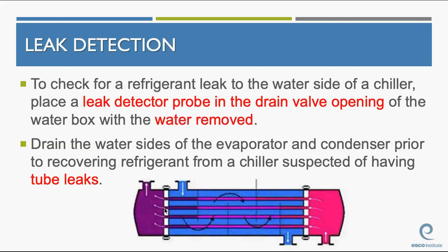To check for leaks to the water side of a chiller, you can place a leak detector probe in the drain valve opening of the water box. Basically, that means the water side of the chiller barrel after you remove the water. So in other words, I can put a leak detector in the drain valve of the water side of this. It's an enclosed enough space where I'll be able to detect if there's a refrigerant leak. But you guys got to do it after the water's removed. If you try putting a leak detector probe in there with water in there, you've broken your leak detector.